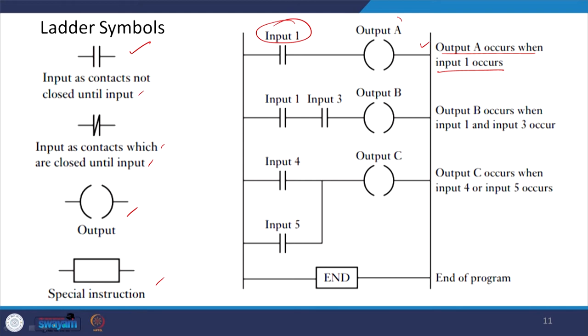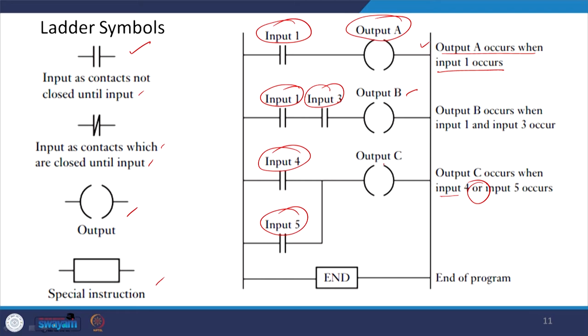These are the ladder symbols used. An input contact not closed until input is available, and an input contact which is closed until input is available, an output symbol, and special instruction boxes. For example: output A occurs when input 1 occurs; output B occurs only when both input 1 and input 3 occur (series/AND); output C occurs when either input 4 or input 5 occurs (parallel/OR). An END box indicates the end of the program.